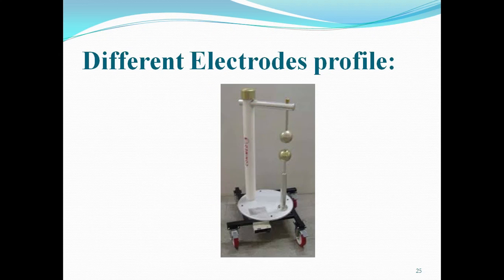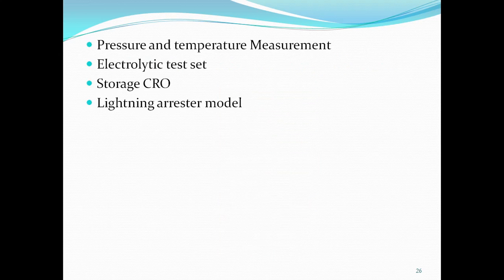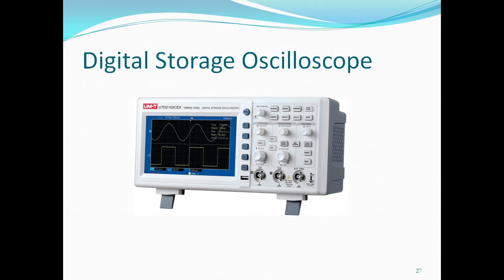In the laboratory, we also have different electrode profiles: sphere arrangement, plate arrangement, point configuration. So we can check the dielectric strength of air with the help of the different electrode profiles. Big spheres and small spheres are there in the laboratory. We also have pressure and temperature measurement instruments, and an electrolytic test set. We also have a storage oscilloscope to capture the lightning impulse voltage, and a lightning arrestor model to understand the concept of the lightning arrestor. This is a digital storage oscilloscope.